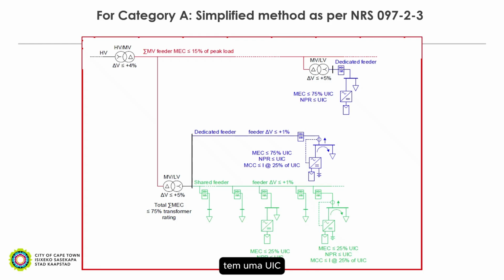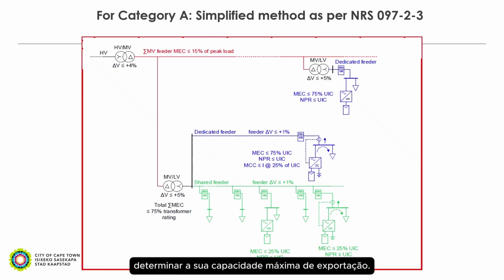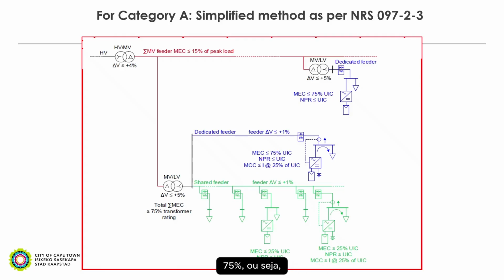He's got a UIC and an NPR of 13.8 kVA, and we're using 25% of that to determine his maximum export capacity, and that should therefore not exceed the 25% for said customers. And the same for dedicated customers, we've got 75%, and the maximum export capacity should not be greater than 75% of the utility installed capacity.